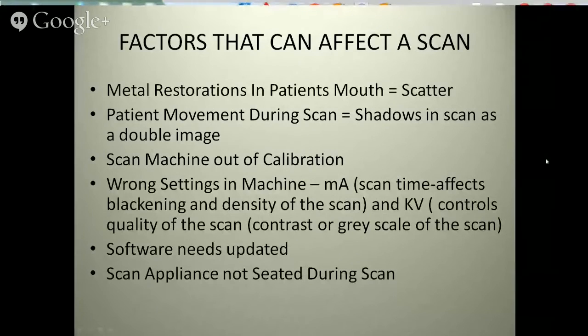The ones that are recommended are going to be accurate, because there's nothing worse than a bad scan. If we produce a guide and the doctor calls up and says the placement of the implant isn't what the virtual plan looked like, and the doctor says the guide was seated, everything was down, I know it was correct, it didn't move - it could very well be machine calibration.